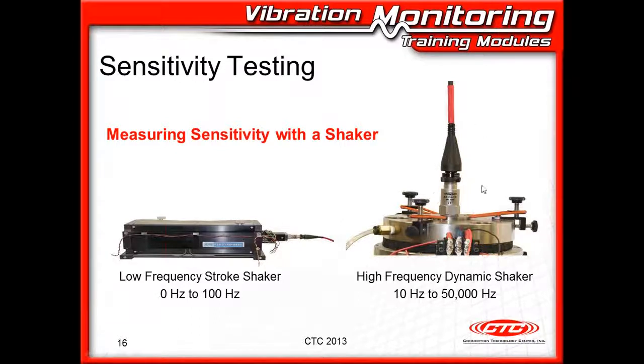Once we get above 100 hertz, we can switch to a dynamic shaker, as we've seen here. This shaker will actually go from 10 hertz to 50,000 hertz. So this does all of our high frequency testing, all of our engineering work for high frequency. It's an air-bearing shaker with a beryllium core, so it's non-magnetic and basically floating in air, and that's how you can get such a high frequency from it.